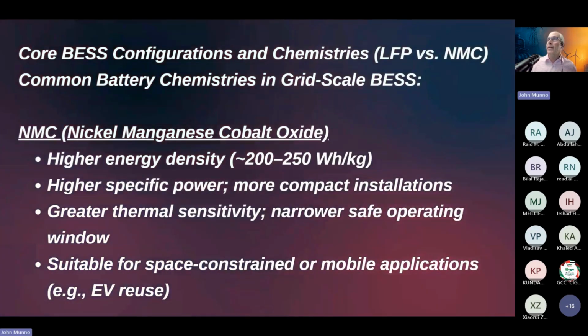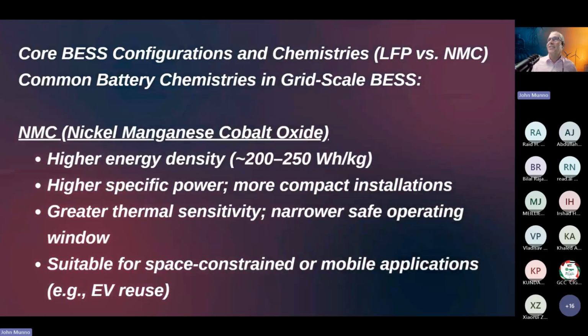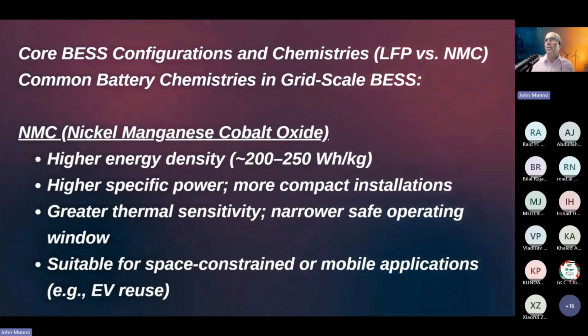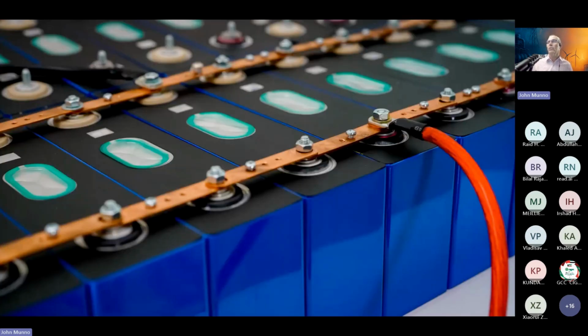Next, we have nickel manganese cobalt oxide. They have a higher energy density, so they can hold more energy per volume of battery, and they're better for compact installations. They have greater thermal sensitivity. That means that they have a narrower, safe operating window. You have to keep them cool while you're operating them to make sure that they don't get too cold or get too hot. They're good for space-constrained mobile applications.